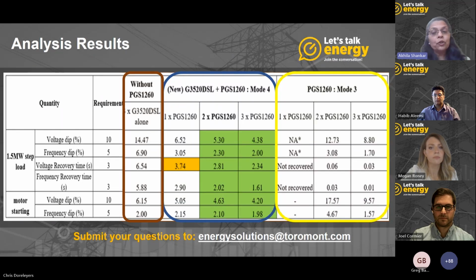So 3 units of 2.5 megawatt standby rated gensets with 2 1260 kilowatt battery energy storage systems provided the required transient performance as specified by the customer for the given set of site load conditions. One point to be noted is that the results that were captured were with the default control tunes. The recovery time in the mode 4 tests can further be improved with tuning of the over frequency, under frequency, or the over voltage, under voltage controllers in the battery energy storage system. And more accurate results can be obtained if the VFDs are also modeled into the calculations.